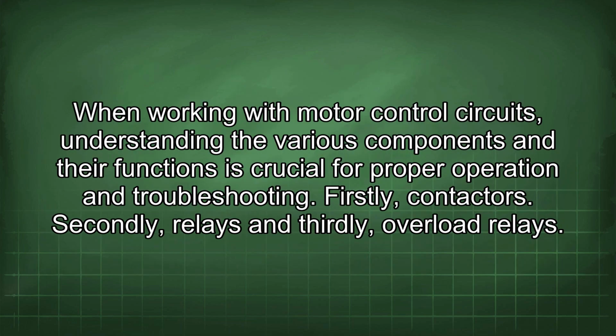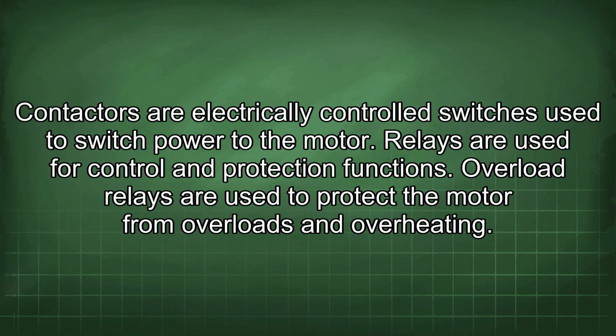When working with motor control circuits, understanding the various components and their functions is crucial for proper operation and troubleshooting. Firstly, contactors. Secondly, relays, and thirdly, overload relays. Contactors are electrically controlled switches used to switch power to the motor. Relays are used for control and protection functions. Overload relays are used to protect the motor from overloads and overheating.